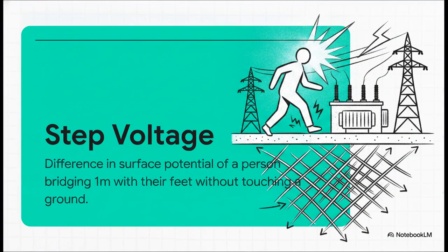Let's zoom in on the physical hardware for a second. Substations step down those insane high voltages, and honestly, the human stakes here are huge. According to IEEE standards, one of the biggest hazards during a fault is something called step voltage. Imagine you're standing in a substation during a massive electrical surge. Step voltage is the difference in surface electrical potential between your 2 feet if they're just 1 meter apart. If you take a step without a properly designed grounding system, that voltage difference could literally be fatal.